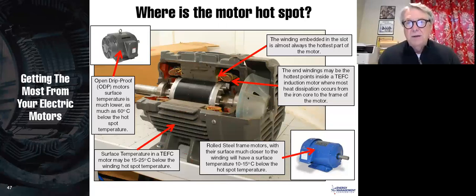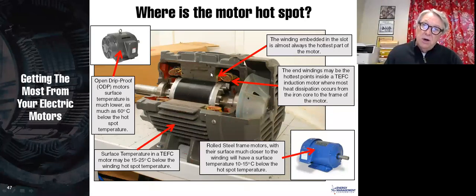Where is it hottest? Well, generally it's hottest in the slot winding. So here's your iron and here's your copper, and right where that winding is in the middle of the iron, that's where your motor tends to run the hottest. And so that's where we put RTDs, and RTDs are a method of directly measuring the temperature. However, sometimes you can have your hottest temperature out here on the end turns of that winding. And we don't really know whether it's going to be on the end turns or here.